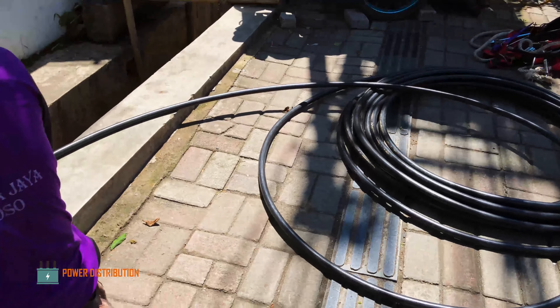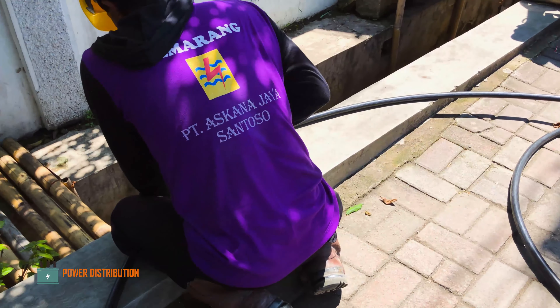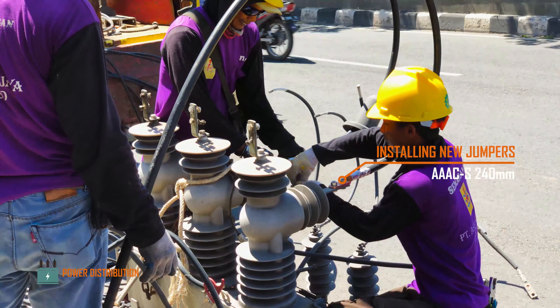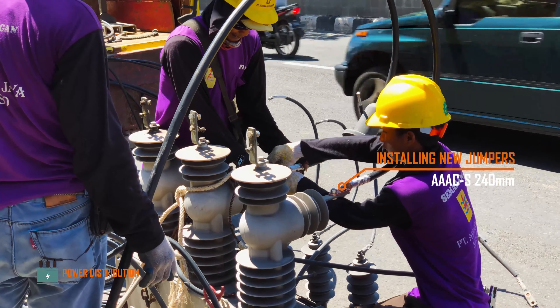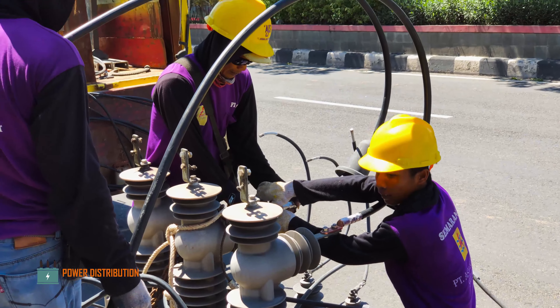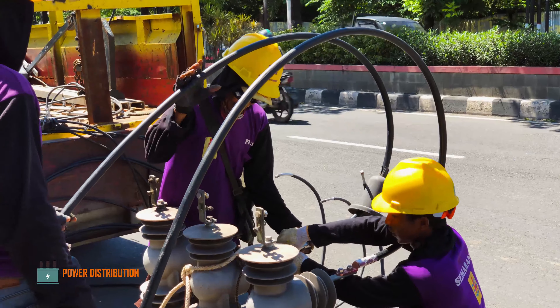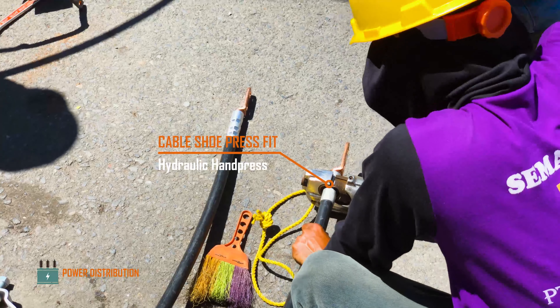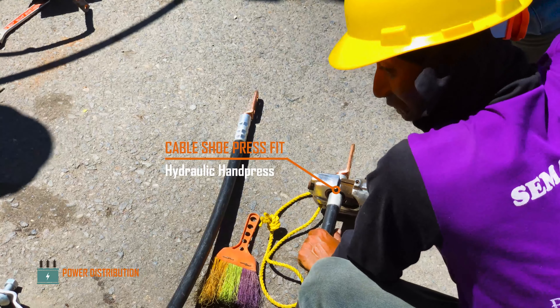This is the stock conductor which will be used as the new jumper. The crew installs the new jumpers to the load break switch, press fitting cable shoes using a hydraulic hand press.